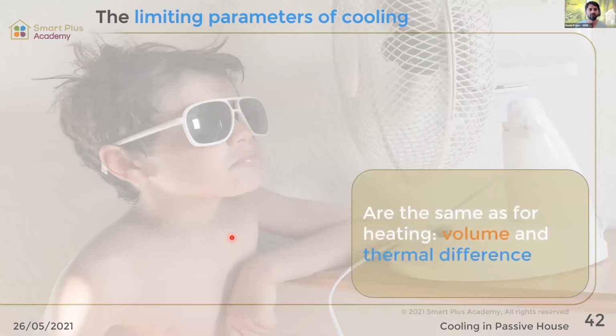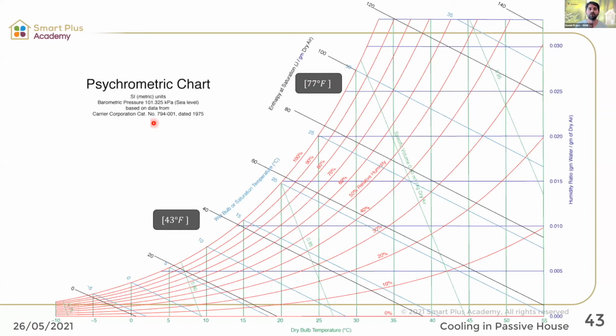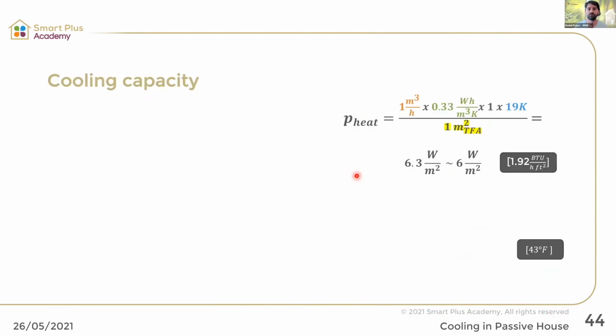Cooling, what is now the limitation of cooling? The parameters are the same as for heating, volume and thermal difference. So when we look at our psychrometric chart, you may have seen that in your course, or maybe you're using it on an everyday basis. Maybe you've never seen it before, I don't know. Here we're having our temperature, 25 degrees, 77 Fahrenheit. When we're going now on the horizontal, we have our absolute moisture content. And when we're coming now to this point, we are reaching the 100% relative humidity. I'm going to the extreme, 25 degrees with 30% relative humidity. We don't want to go to a lower relative humidity. And then I'm going to the other extreme where we're reaching 100% relative humidity at 6 degrees. So it's the maximum capacity, that span between 6 degrees and 25 degrees is the maximum thermal difference we can use for cooling. Here's now our formula for that again.